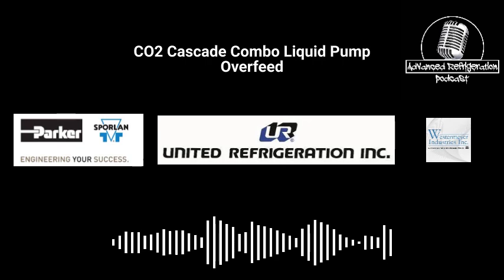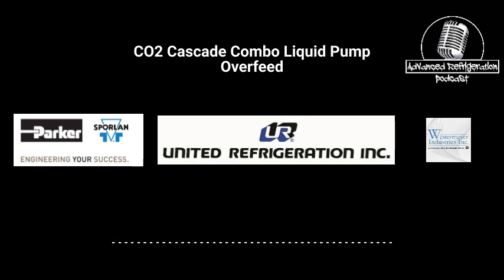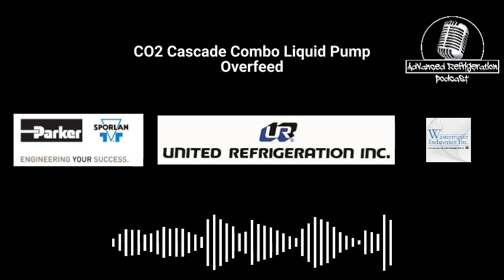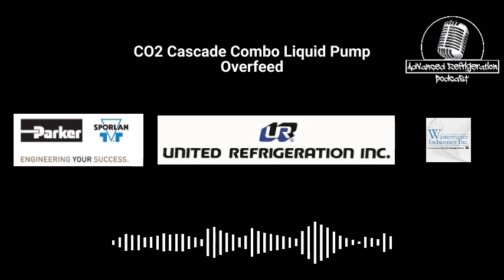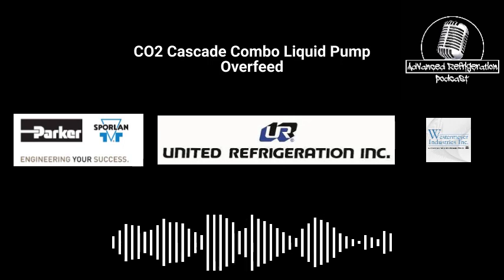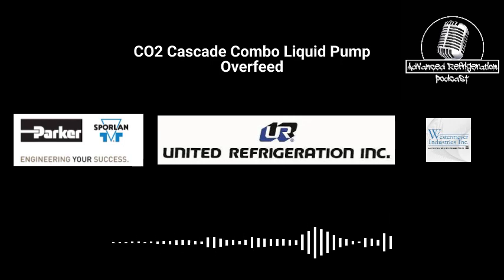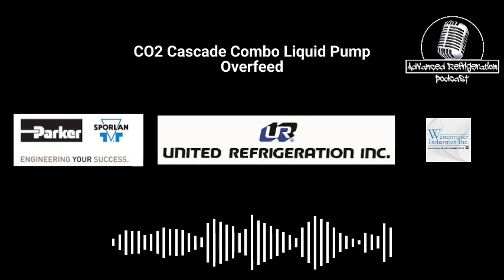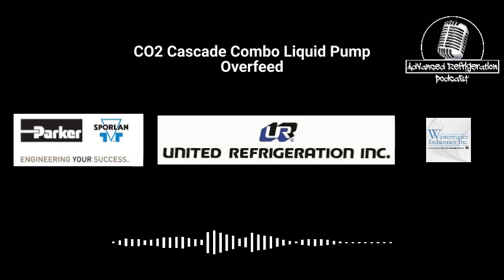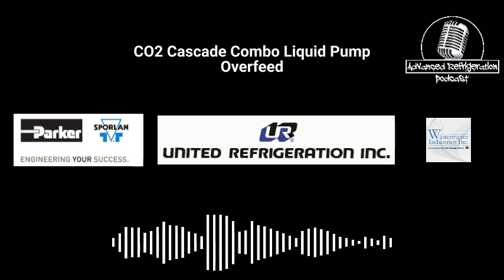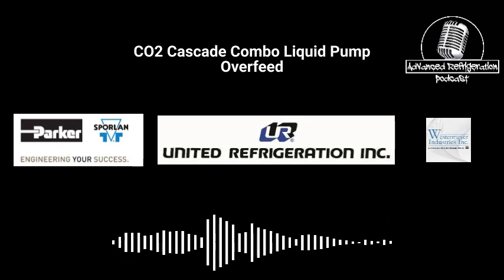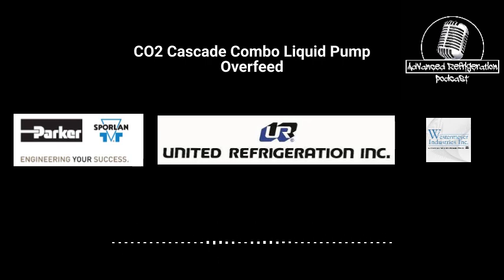Yeah, so it sounds like what you're describing is a liquid pumped overfeed rack, basically, is how they're doing it. I've seen the Carnot version, and the ones I've seen are a little bit different. Like I said, they're using the HFO to cool the actual plate and frame heat exchanger, running the discharge of the compressor through there, dumping the cooled liquid CO2 into the receiver, and then using that to pump it out. They just use the recirc to dump into the receiver, and then it gets pumped through the system. So that's how they're doing it.